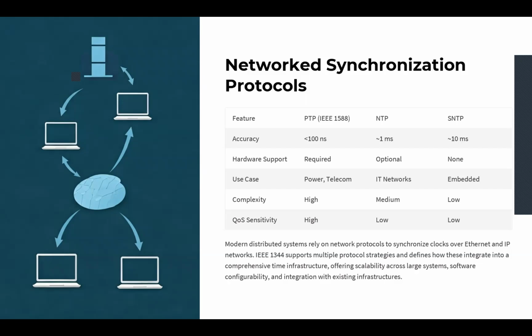Now we have hardware support. In PTP it is required for best accuracy. NTP has optional hardware support, but SNTP doesn't need that. We use PTP normally in power and telecommunication. NTP is normally used in IT networks, and SNTP is normally used in embedded systems. On the other hand, PTP has high complexity compared to NTP, which is medium, and SNTP is low complexity. PTP has high jitter or delay sensitivity, while NTP and SNTP are much lower on that. Now let's understand what this means. Let's go deeper into that table.